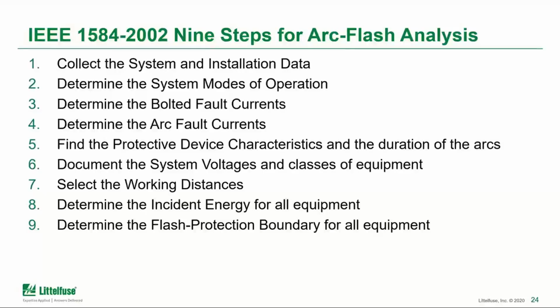Now, just to review the actual steps for the arc flash analysis. The IEEE 1584 standard does have specific steps that it goes through. And just as a point of reference, this slide here is showing the 2002 steps. You first always start by collecting the system and the installation data. And for a lot of existing applications, that is going to be the bulk of the work, to make sure that all the data is correct, that you have the accurate information from your existing equipment.